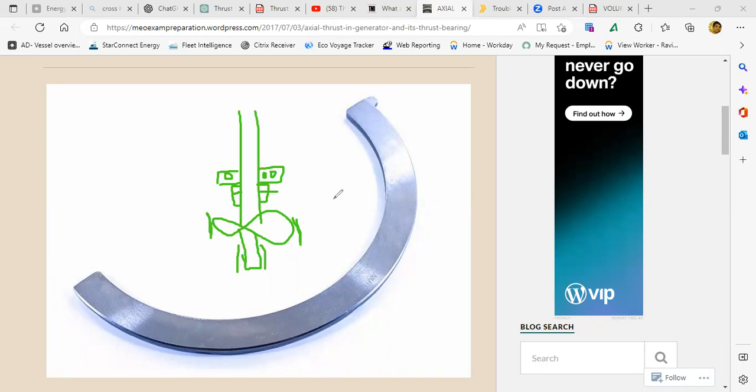On the motor. Now, let's say this is the intermediate piece, correct? Here the intermediate piece sits, here the motor sits. In the motor there is one bearing here and one bearing here. This is the motor shaft, and both are ball bearings. But I cannot find a thrust bearing in the pump. Does it exist? Any idea?